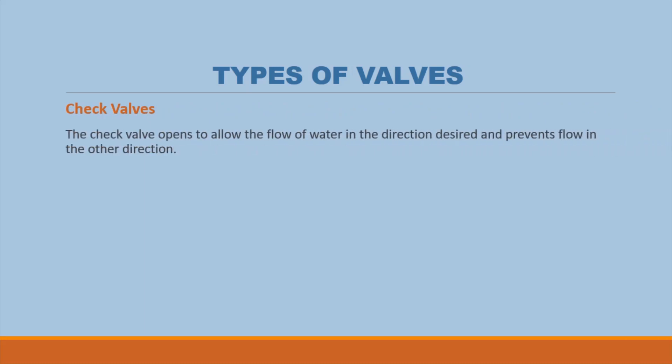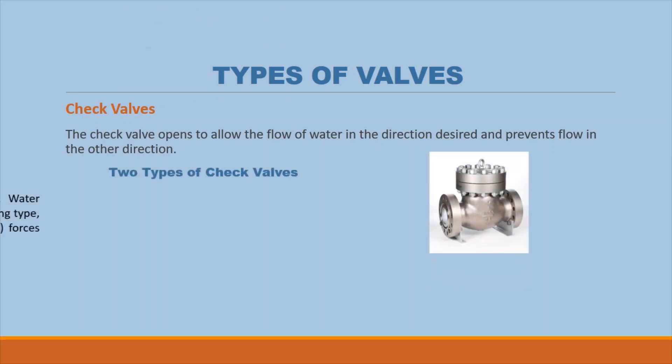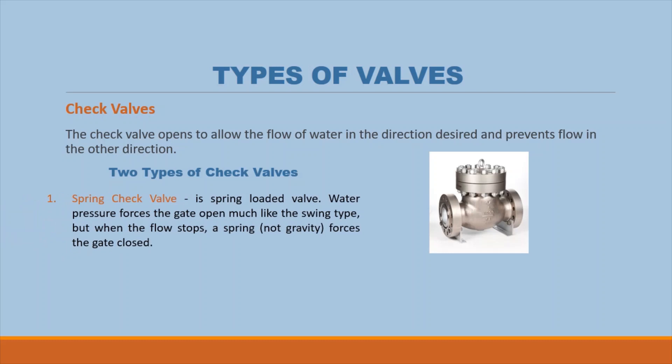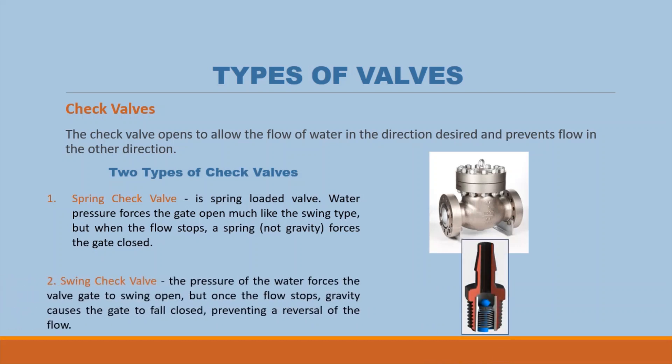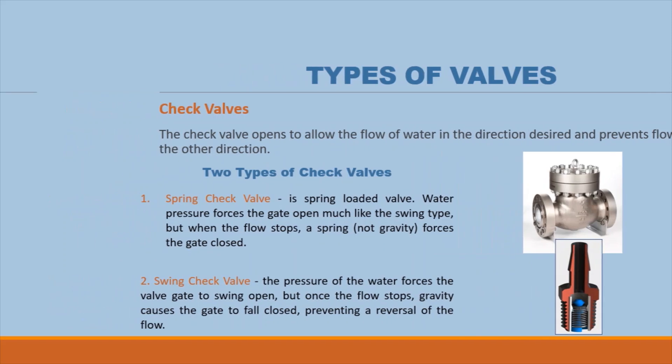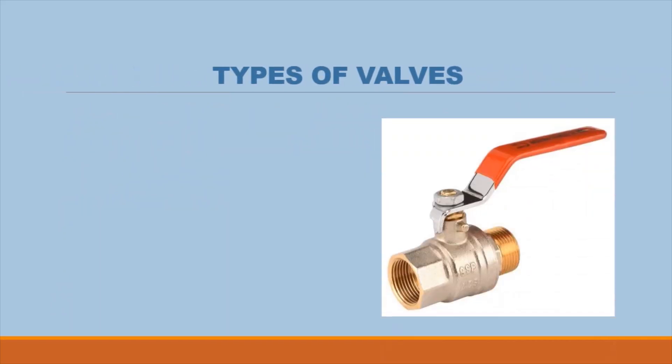Check valves open to allow the flow of water in the desired direction and prevent flow in the other direction. There are two types: the spring check valve is spring-loaded — water pressure forces the gate open, but when the flow stops, a spring (not gravity) forces the gate closed. The swing check valve: water pressure forces the valve gate to swing open, but once the flow stops, gravity causes the gate to fall closed, preventing a reversal of flow.